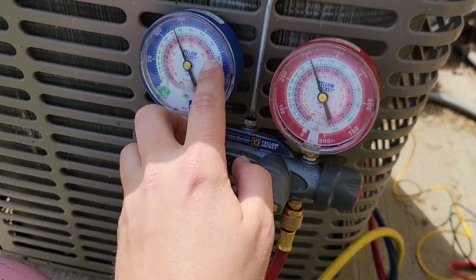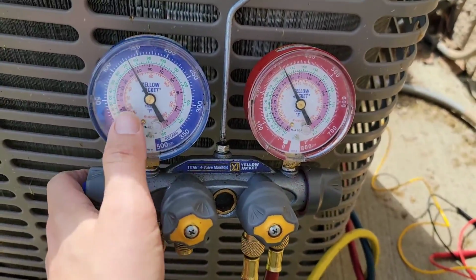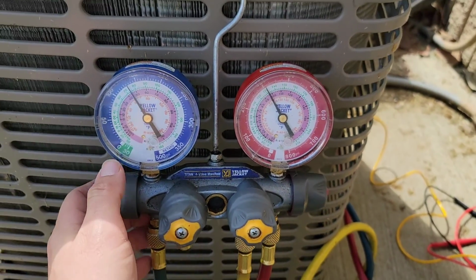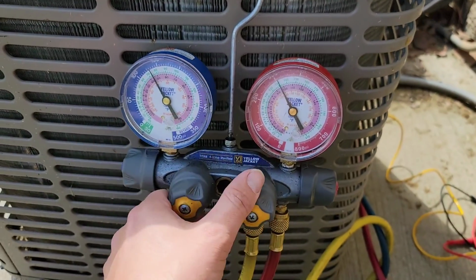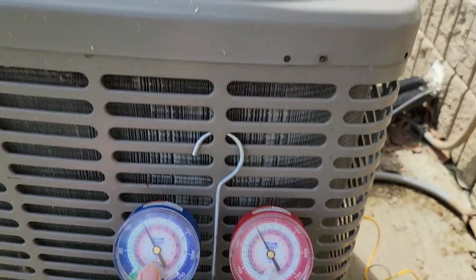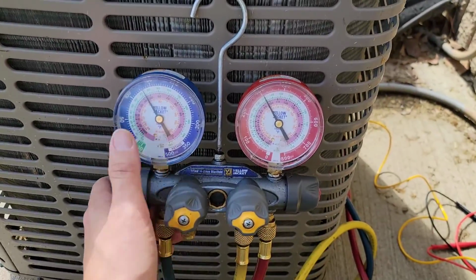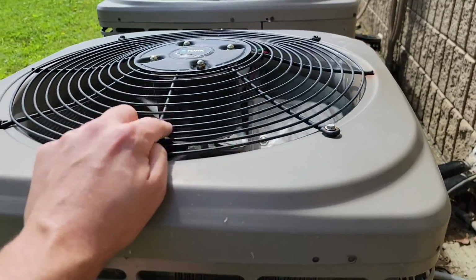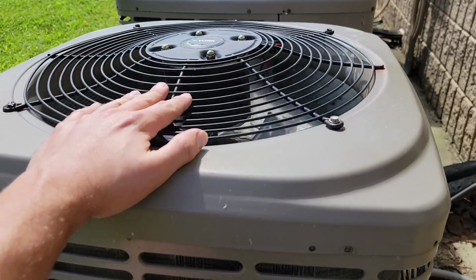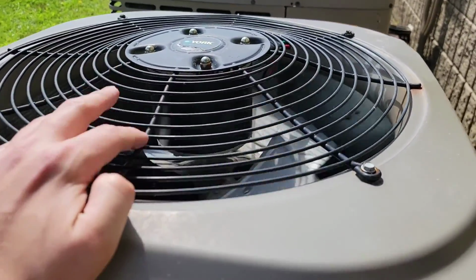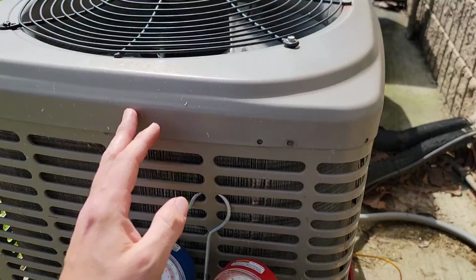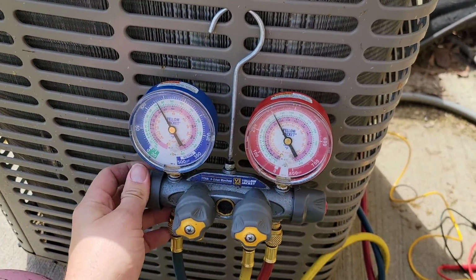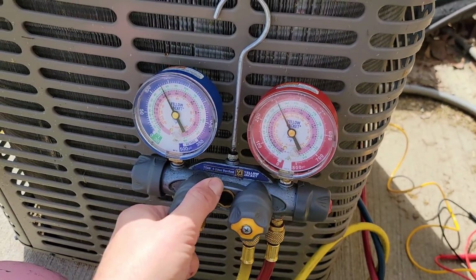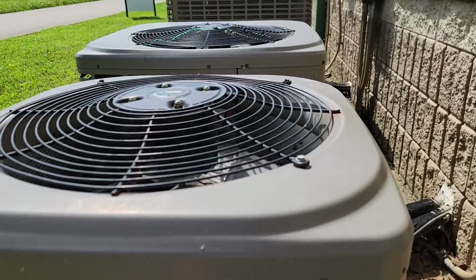I wanted to show you the difference between R22 and 410A pressures in the same video. That barred unit on the trailer earlier was R22. This split system is R410A. This is for a server room. If you want to know more about head pressure control, because that's what this has on it, a low ambient kit, then check out my video on my playlist, Tips for Technicians. I have a video on head pressure controls.